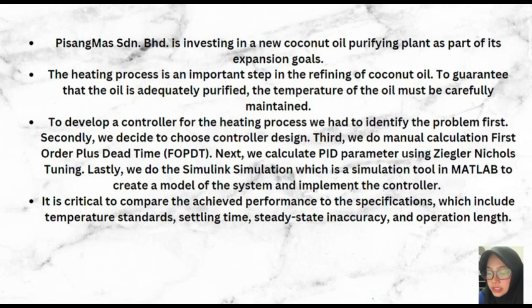To develop a controller for the heating process, we identified the problem first. Secondly, we decide on the controller design. Third, we do manual calculation, first order plus dead time. Next, we calculate the PID parameters using Ziegler-Nichols tuning. Lastly, we do the simulation, using simulation tools in MATLAB to create a model of the system and implement the controller. The simulation helps to evaluate the performance of the controller and its ability to meet the specific requirements. For the final results, the simulation needs to be analyzed and the performance of the controller evaluated. It is critical to compare the achieved performance to the specification, which includes temperature standards, settling time, steady state inaccuracy, and operation length.